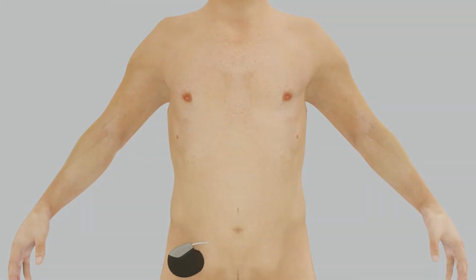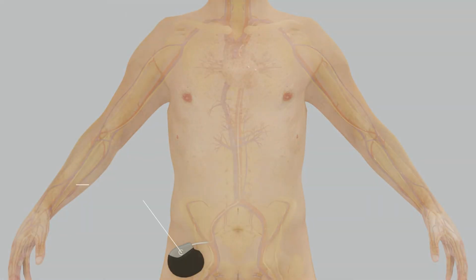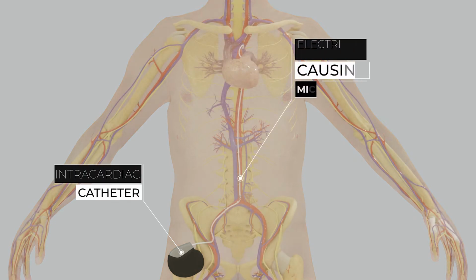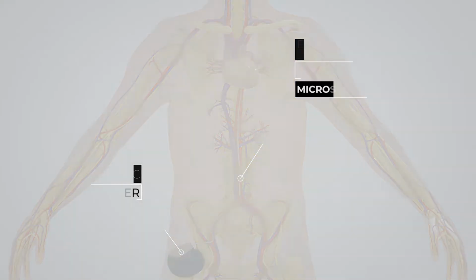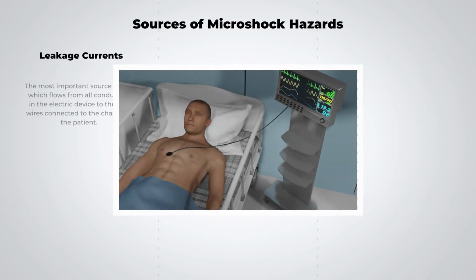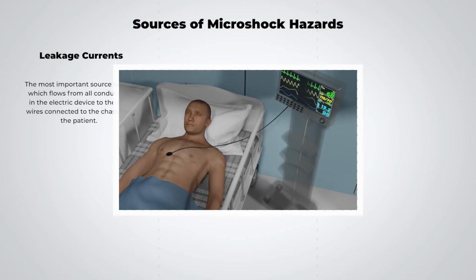The second type of shock hazard is microshock. Damage from this is due to an electrical current being delivered directly to the heart, for example, through an intracardiac catheter. Sources of microshock hazards are leakage currents. Most important source of leakage current is that which flows from all conductors in the electric device to the lead wires connected either to the chassis or to the patient. If a low resistance ground wire is available, leakage current flowing to the chassis flows safely to ground.